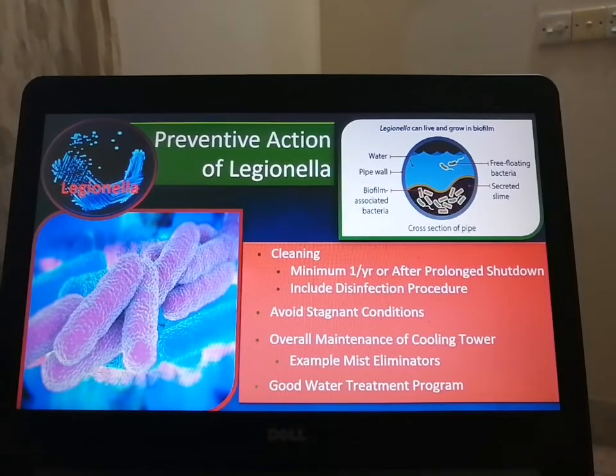Generally the vapor does not carry the biocide or bacteria, but the water droplets do. So in cooling tower design, if we can apply a proper mist eliminator or drift eliminator, we can minimize the water droplets coming out from the cooling tower. That is also a kind of preventive action to reduce contamination and reduce the probability of Legionella infection.